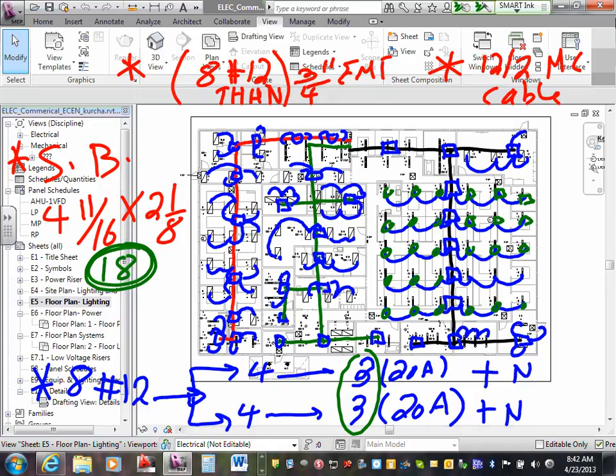Now, Jeff is looking at me and says, Chad, I could have MC the sucker, all of them together. You could. If you can use MC for everything, no EMT conduit, but I'm telling you, I need EMT conduit. If you want to MC it, guys, you can MC with 4. That will be 12-4. 12-4 will give you 3 circuits. Then you start taking your MC cable, moving it from one to another, all the way, but you can carry only 3 circuits in the cable. Here with conduits, I can carry up to 6 circuits, even more. I can carry another 3 circuits without exceeding the code.